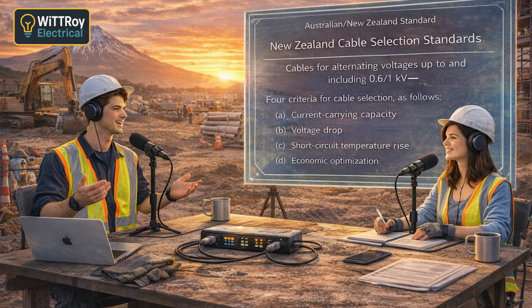Correct. All right, let me try to summarize everything. Go for it. So first, we check current carrying capacity using tables, then apply derating factors, then check voltage drop using the formula, then check short circuit if needed, and maybe consider cost. That's an excellent summary. And the final cable size must pass all checks. Exactly. I think before I was just jumping around, now it feels more structured. That's the goal. Yeah, like everything links together. It does. Current, heat, voltage, faults, it's all connected.